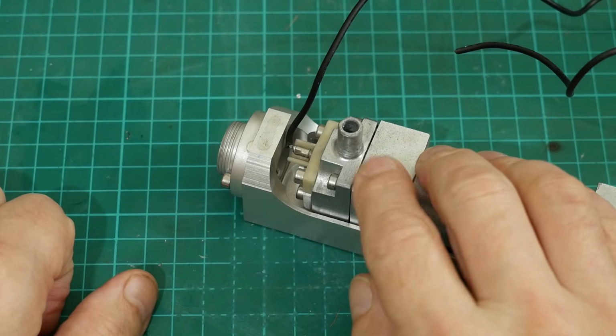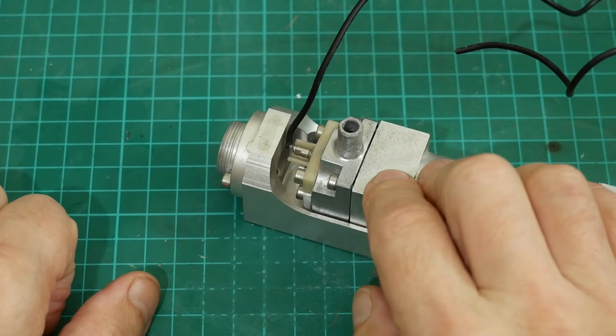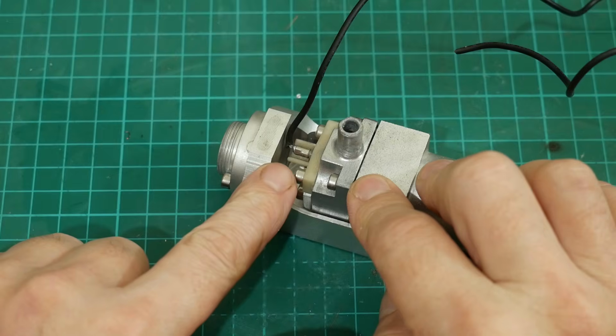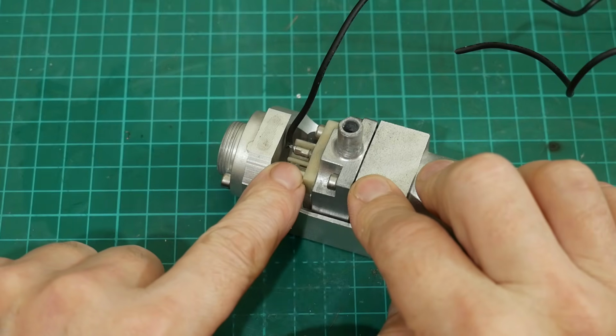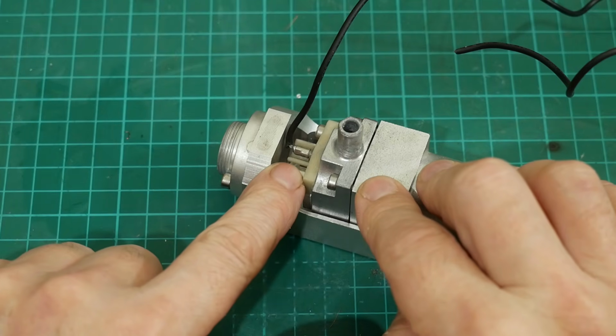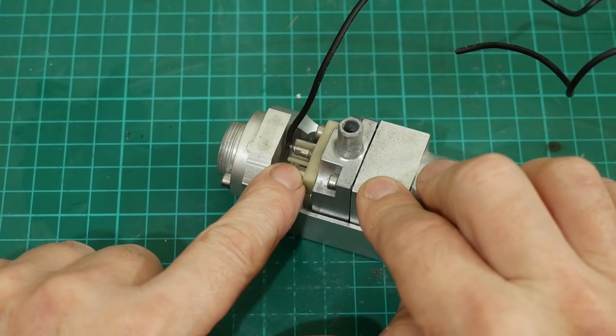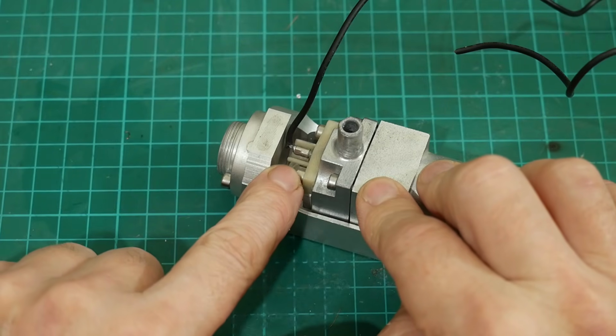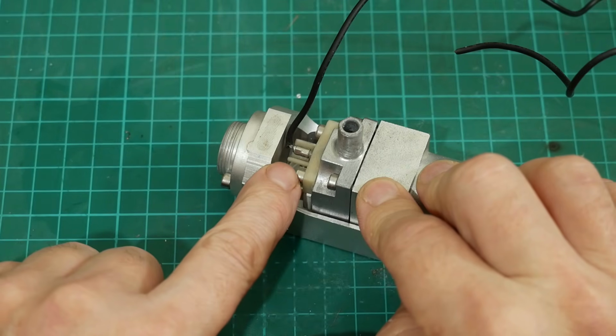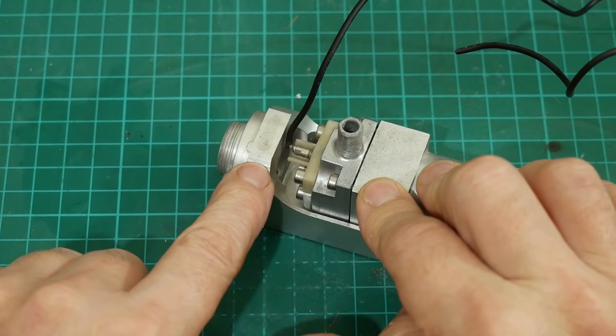On the subject of bad design, another modification I need to make is to improve the clearance at the end of the lamp here. This is the electrode for the lamp. Now, the lamp will be provided with somewhere in the region of 800 to 1000 volts or so, and the clearance, even at that, is too small. We're looking at maybe 4 millimeters here between the end of the lamp and the chassis.